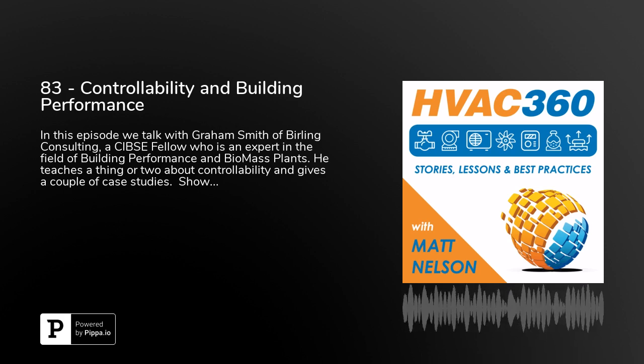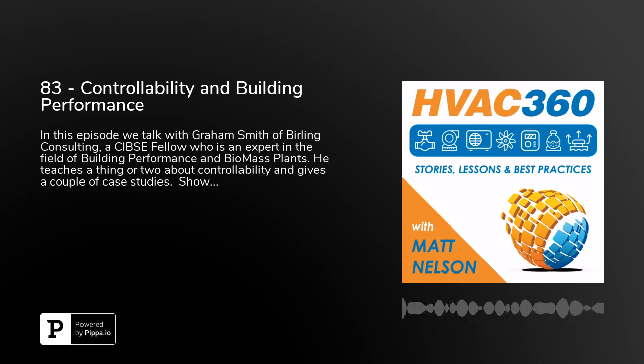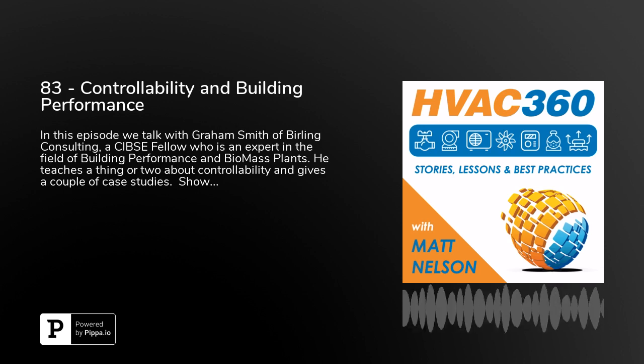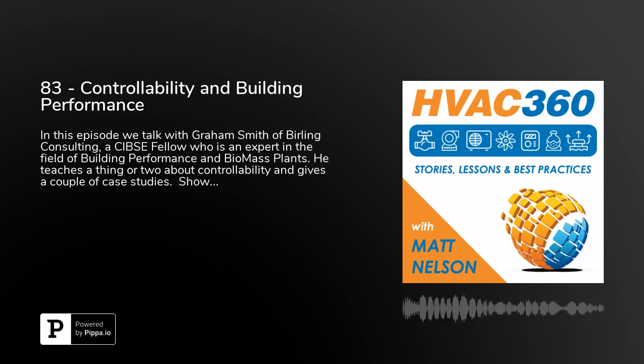I was asked to go and have a look. I went to site, started asking some questions, and after about 15 minutes I reached the conclusion that the primary problem was the deadband between heating and cooling had been set too close, causing the system to overlap between heating and cooling, which was wasting about a quarter of their energy. So we reset it in one part of the building, which took probably another quarter of an hour, and that seemed to work. So it didn't need a new building management system at all. All it needed was setting up properly.